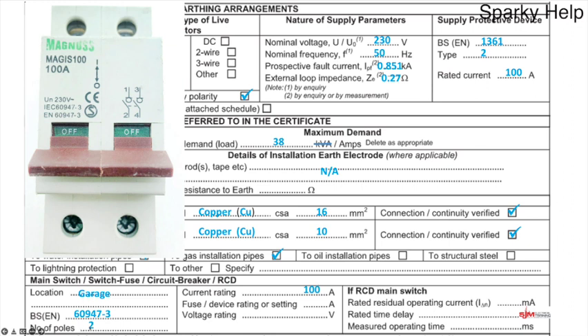So 2 poles, you'd be checking against your earthing system and your supply voltage, making sure 2 pole was enough, because it could be a 3 pole, 4 pole, if you're talking 3-phase 4 wire, and depending on the earthing system and checking against the regs could determine whether that particular device was correct or not. In this particular case, our current rating is 100 amp, which coincides with our 100 amp up here. So if we had a 160 amp fuse, we would be wanting a 160 amp main isolator. Otherwise, it wouldn't be capable of doing the job. So that bit is check, fine.